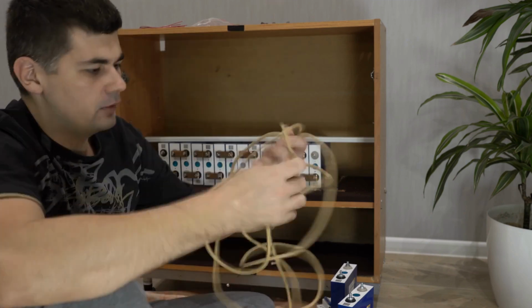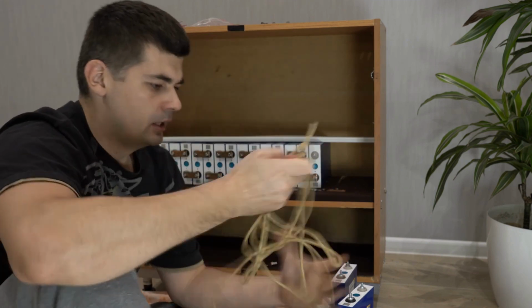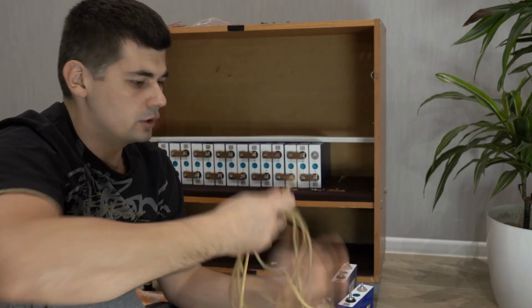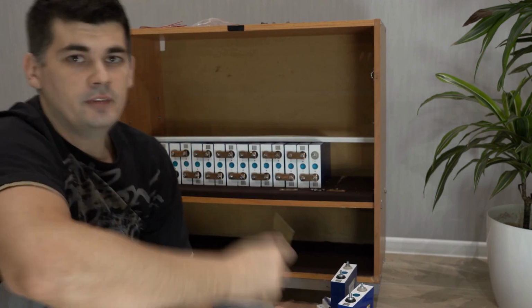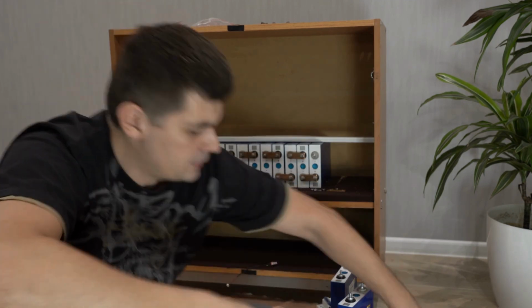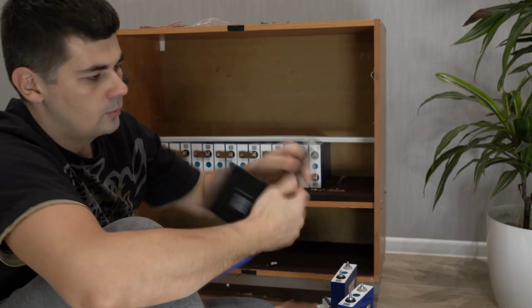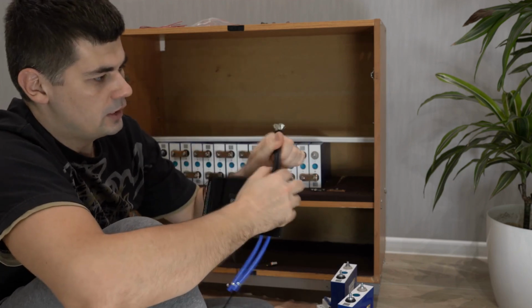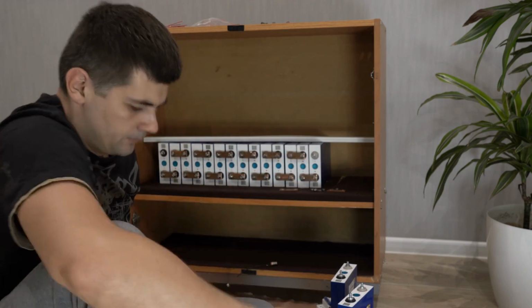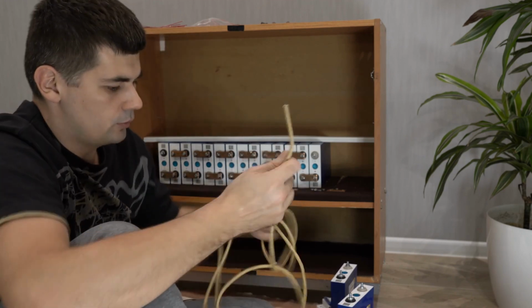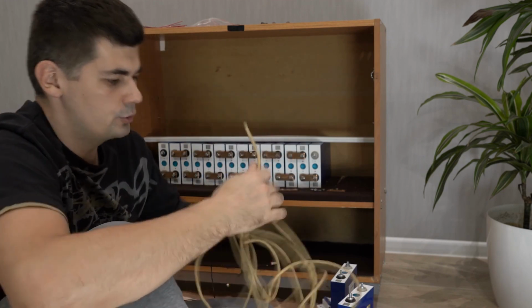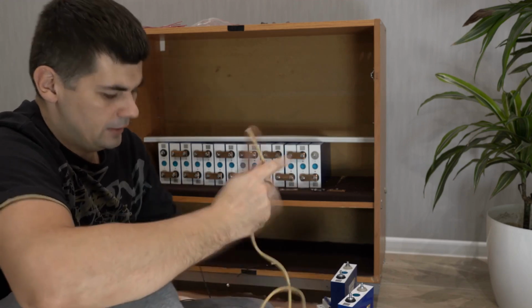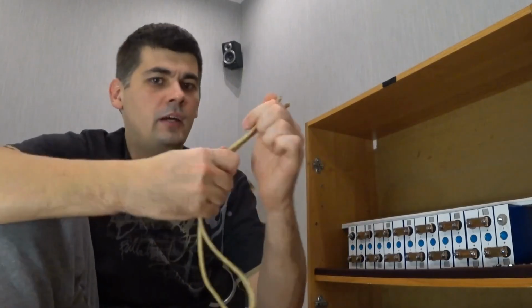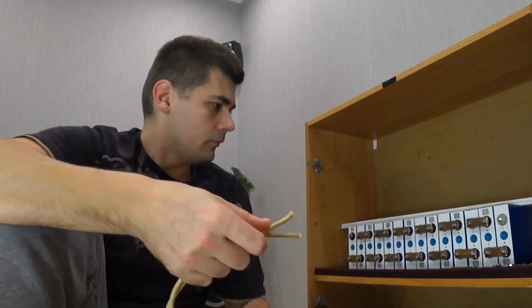Now, what else do we need? We need to put terminals on the wires. I have used wires, various pieces, I'll cut longer ones as needed. For the inverter connection, the BMS has 2 parallel 10 square millimeter wires, meaning 20 square millimeters total. I also took 10 square millimeter wire, I'll run 2 in parallel for positive and 2 for negative, and connect them to the inverter.